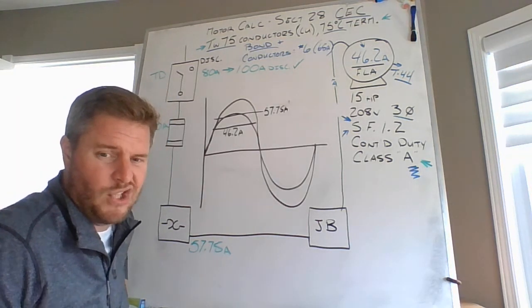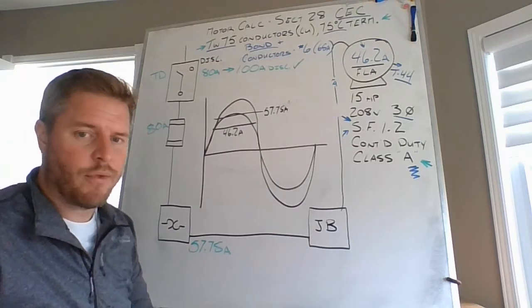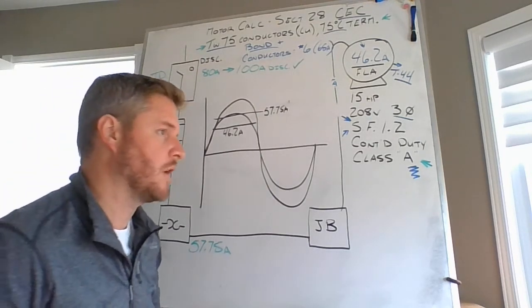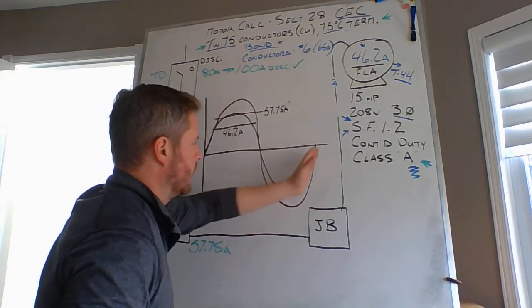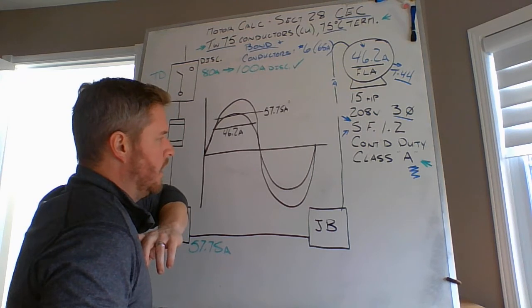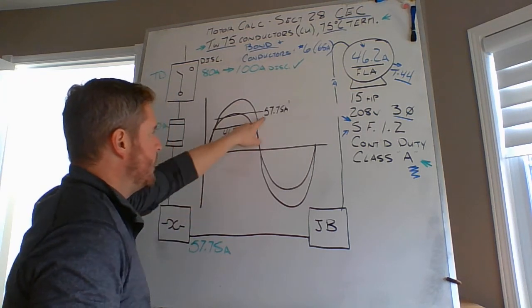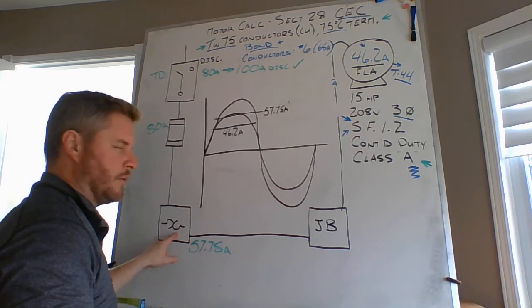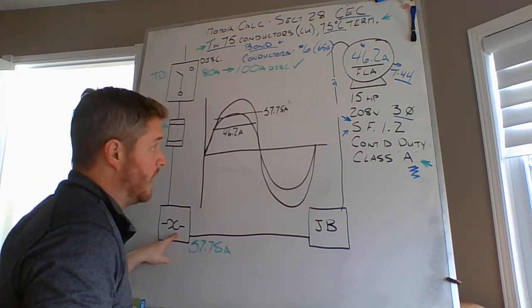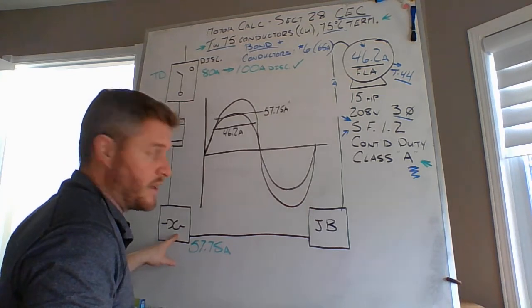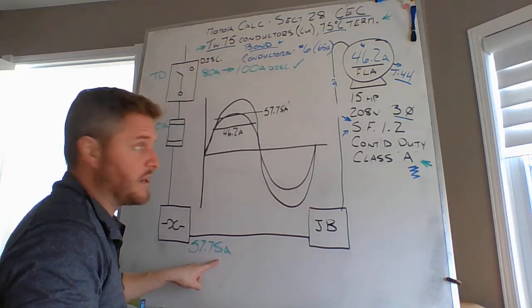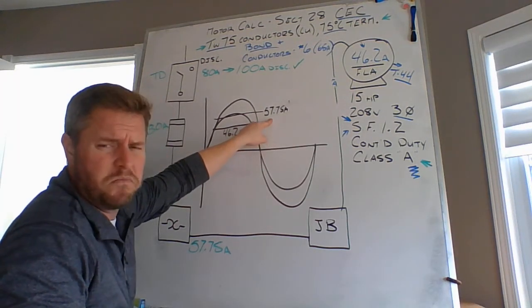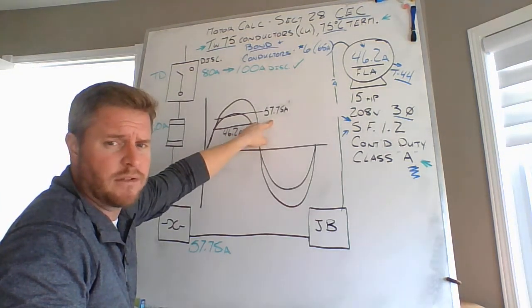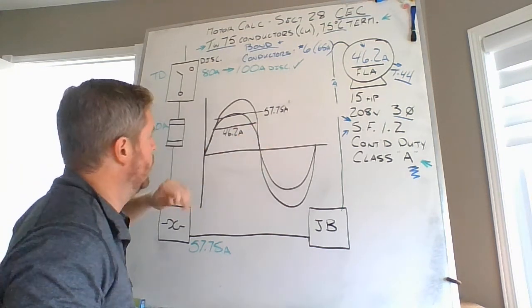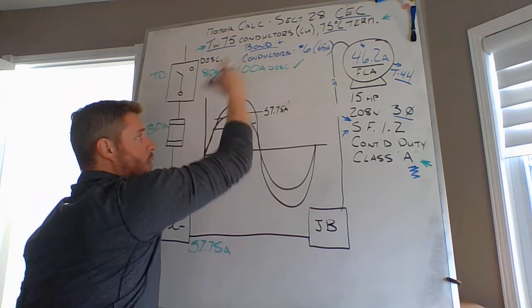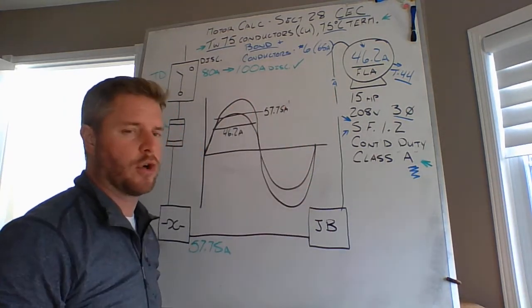That's okay. Your overloads, they're observing that. They're watching that ampacity. They're watching that expanding contactor magnetic field. They're following that current traveling towards the motor in an AC system. 57.75, that's not going to hurt your overloads. They're not going to trip at that point in time. They're going to be saying, hey, listen, we're getting really close. Be careful of this. 57.75, you're drawing 57.75. Okay. That's a little heavy, but don't do it any longer. No big deal.